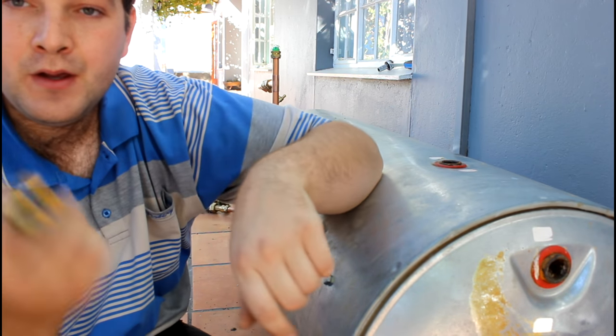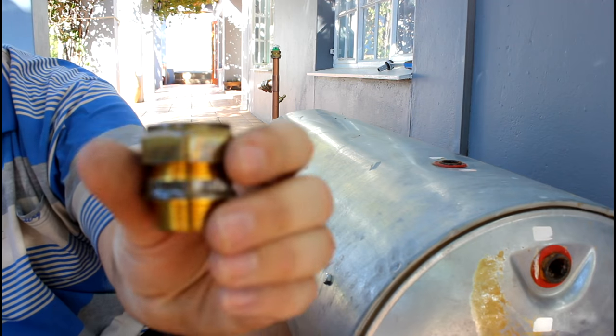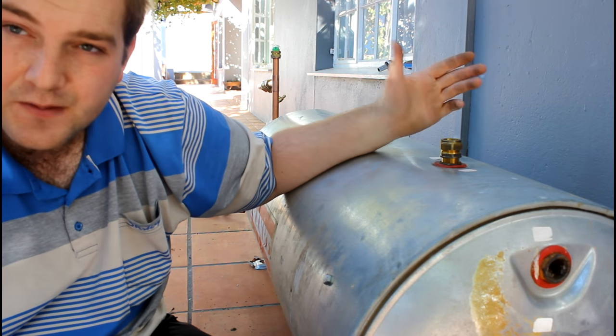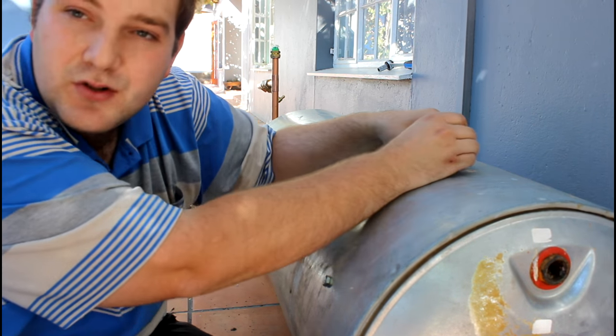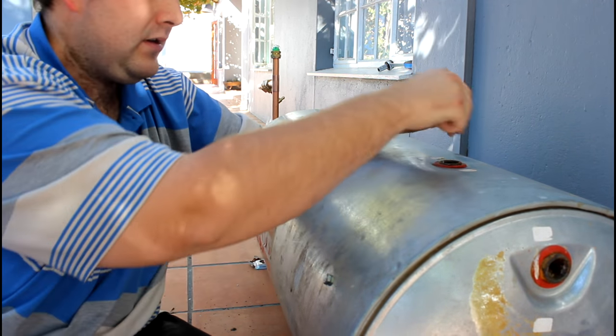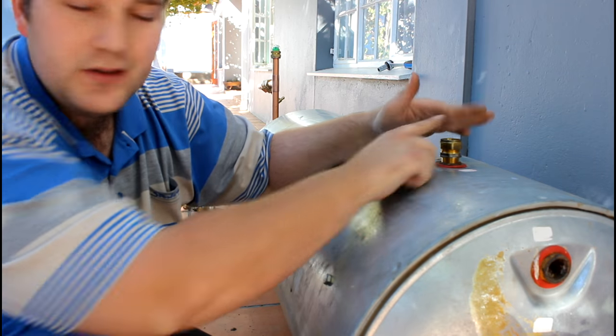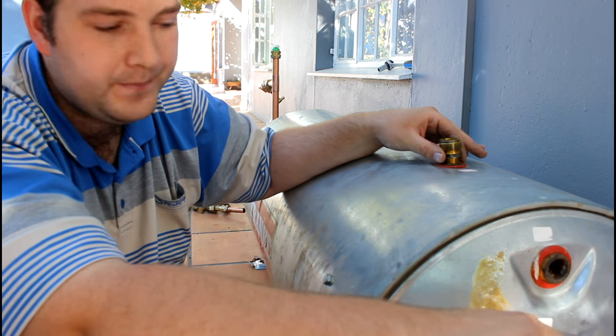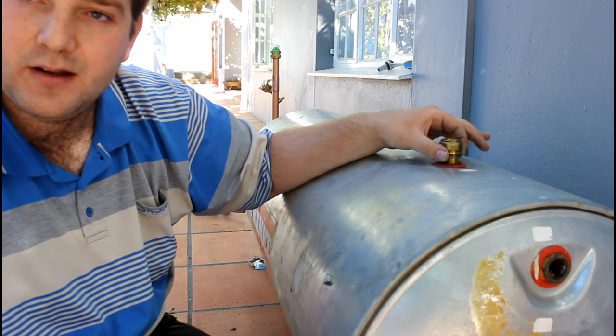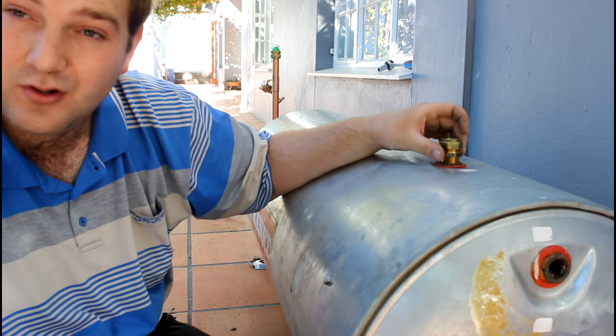Another tip: when I install a geyser I always use Conex fittings against the geyser. Because if something happens to the geyser in future, the plumber comes and just needs to open these fittings - it's cost-effective to put in a new one. For example, if you get a new geyser where the connections are in different positions, you just disconnect and reconnect. Where if you had soldered it to the geyser, it's going to be a lot of cutting and soldering work to do.